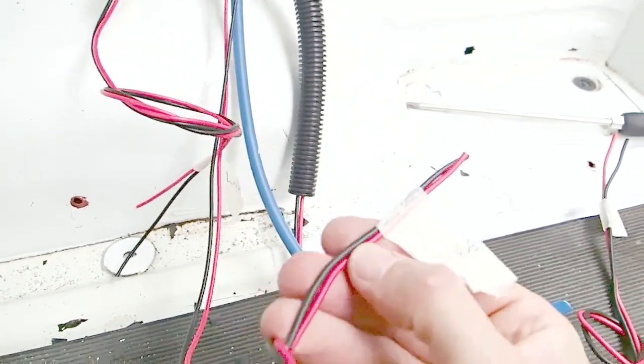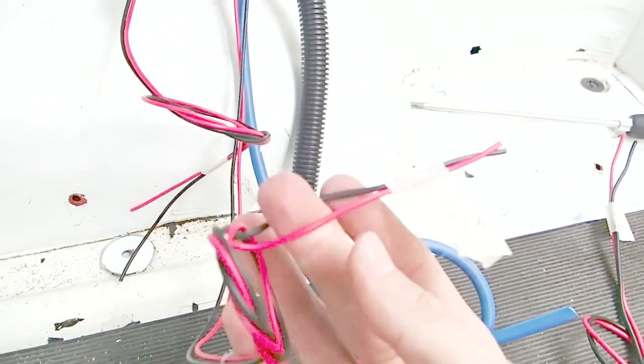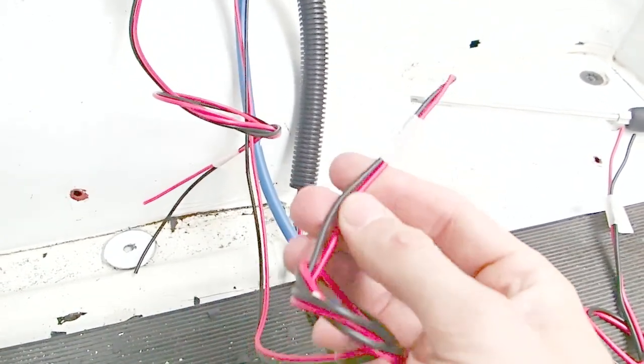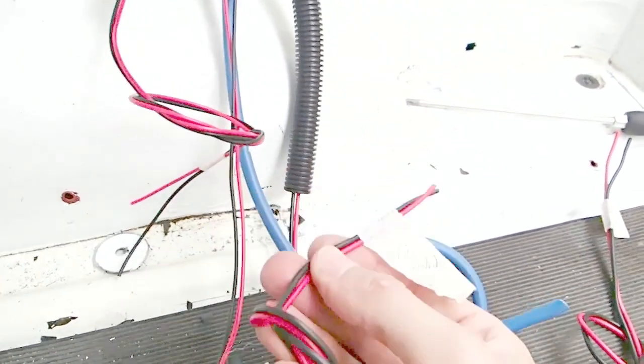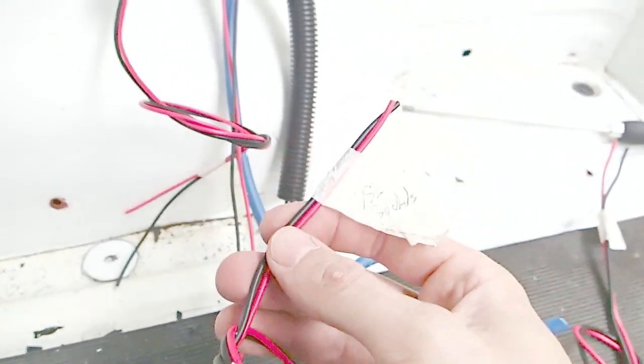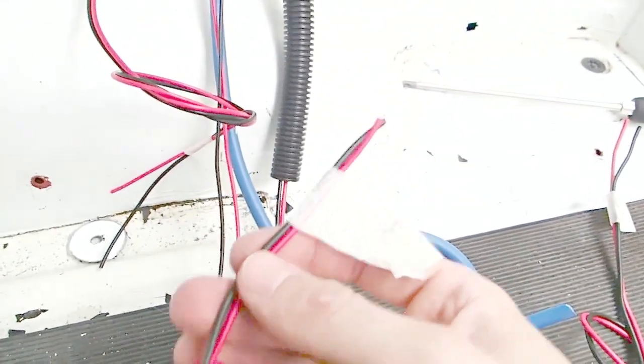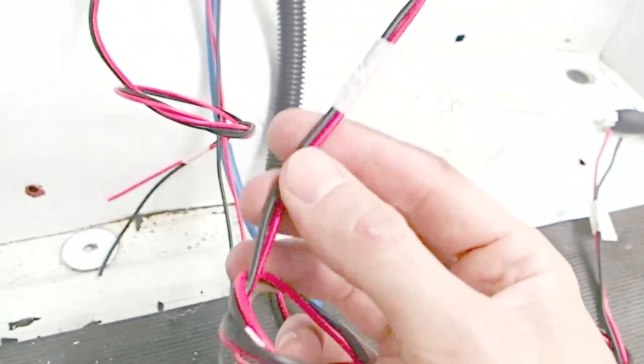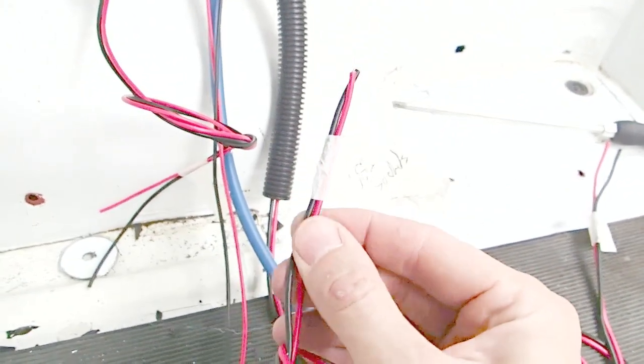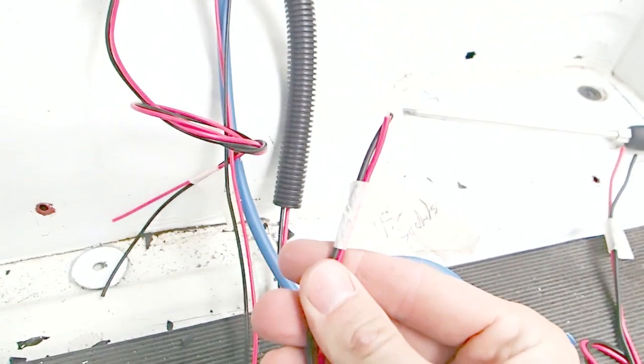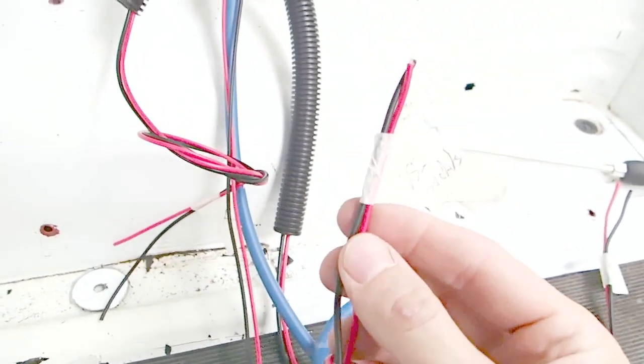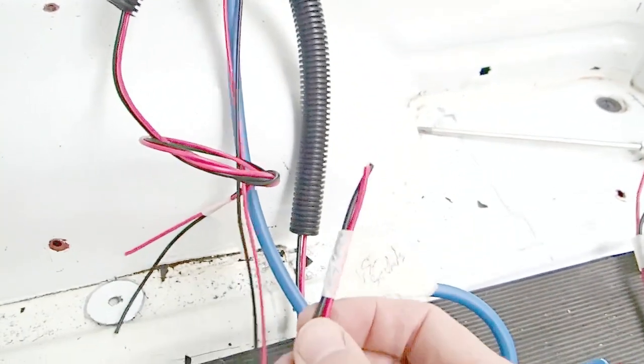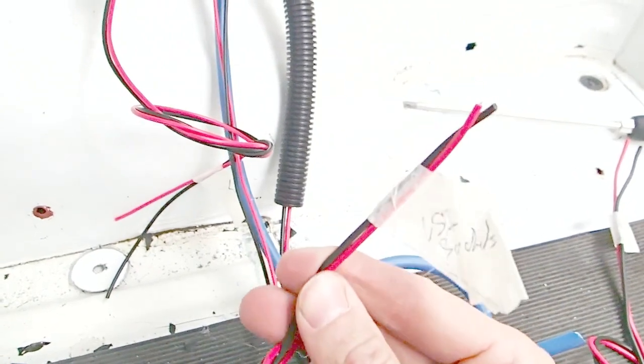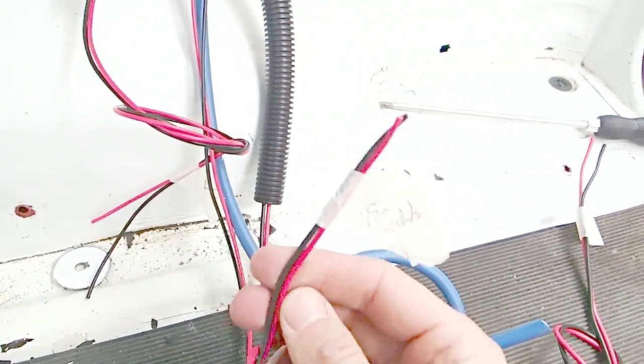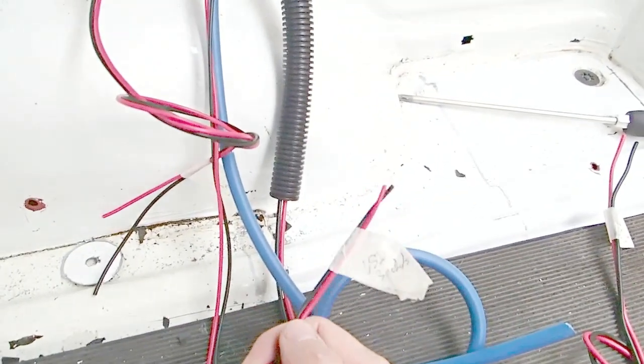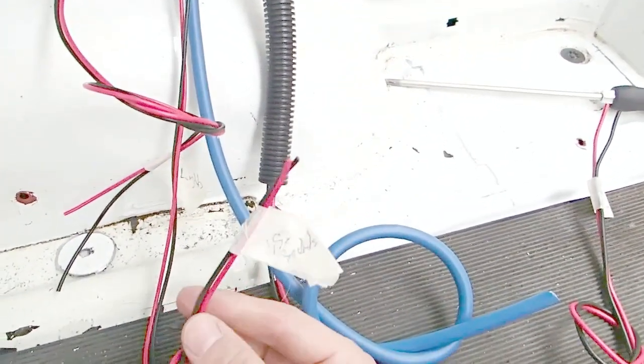They're very small cables actually. I would have used 5 amp, but they didn't have 5 amp in the store, so I used the nearest thing up from that. When working out which cable to use, take the power draw — say 3.1 amps for my USB sockets — and add an extra 25%, so around 4 amps. A 5 amp cable will safely handle that. It doesn't do you any harm to use bigger cables, but it will do harm to use smaller ones. Using anything smaller than 5 amp, I don't even know that exists. What happens is it heats up, gets really warm, melts the insulation, and you get breaks — that's when you can start causing fires. So always go for bigger cables than your power outlet is going to draw.